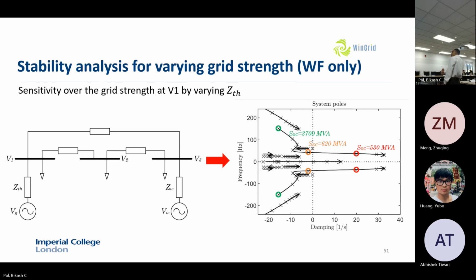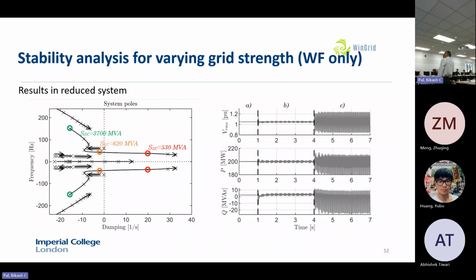the STATCOM. And then as we vary the fault level, that is from the synchronous generator, this ZTH, how some of the poles are moving. So for a strong grid, all the poles are on the left half. For a weak grid, if you go to 530 MVA, then you see that we are crossing this. So in a weak grid, the interactions from the wind are now more visible. So that is the stability analysis for varying grid strength, wind farm only.